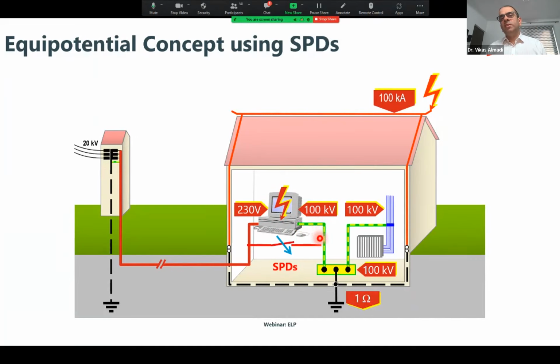Bypassing the current or equalizing the voltage is one and the same thing. So you need to have a switch-like arrangement, which is normally off because you cannot connect line and neutral and earth together. Normally off. In case of surges, it will turn on, and then when it turns on, the other side also gets the same voltage. That means on the equipment side, you don't see any change or any difference in the voltage. So no current will flow from the equipment. Current which would flow through the equipment will now flow through the switch, and this switch is nothing but the SPD. If this is rated for 10/350, it is known as lightning current arrestor. If it is rated for 8/20 microsecond, it is known as surge arrestor.